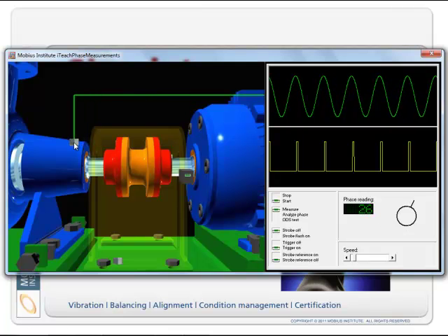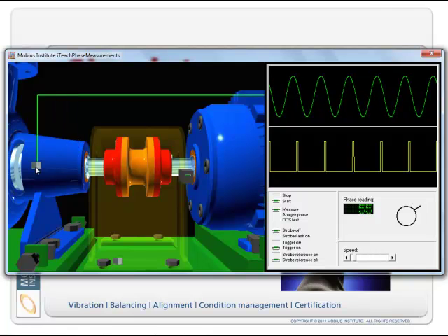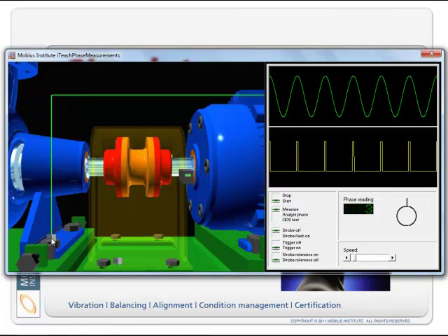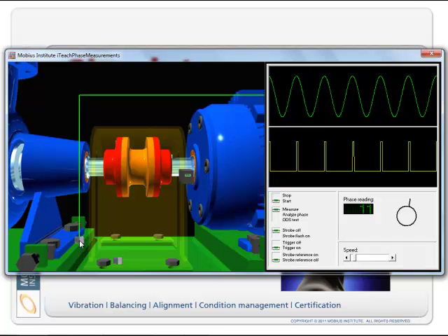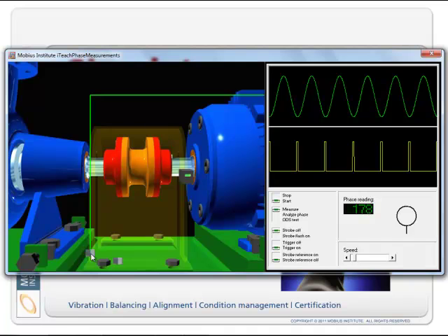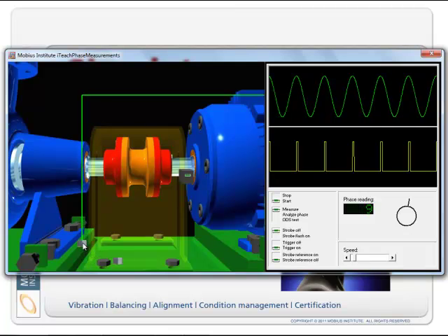But I can move it in different places. I can also do a little trick here. So let's put the vibration sensor here. We'll put it down in these hold-down bolts. Good, about zero. Put it here. Yeah, about zero. Let's put it on this part. Yeah, it's still around about zero. Let's put it down there on the base. Oops. It's just changed by 180 degrees. And that would tell me that there must be a crack. It must be separated between this plate, and there's movement here and no movement down there. So there's therefore a 180 degrees phase shift.